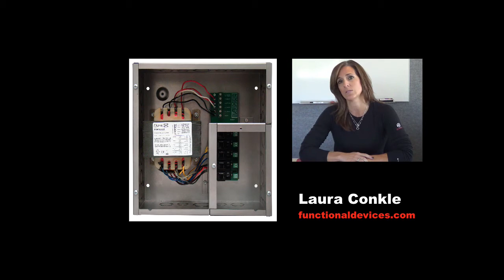Arc flash, by definition, is an undesired type of explosion that can cause serious damage, not only to the equipment but also to the person working on it. So what we're trying to do here at Functional Devices is make an enclosure where the high and low voltage are separated, which you'll see in the picture on screen in a second. The idea behind separating the voltages is that you don't have to put that suit on for protection if you need to go into the low voltage compartment.